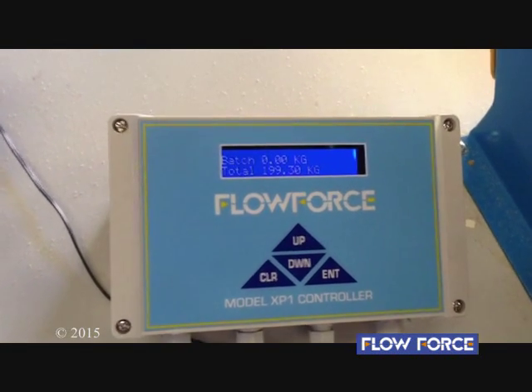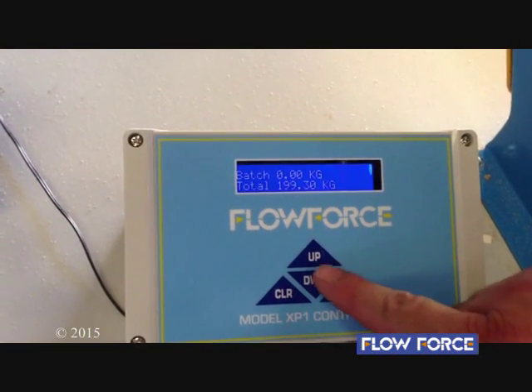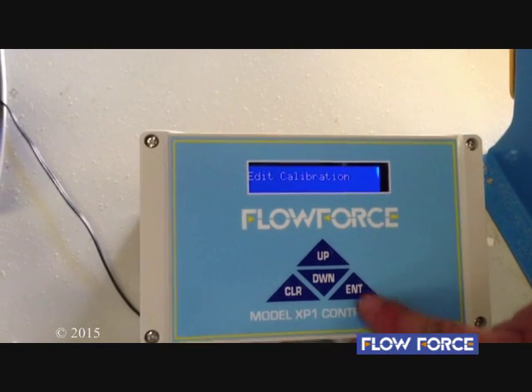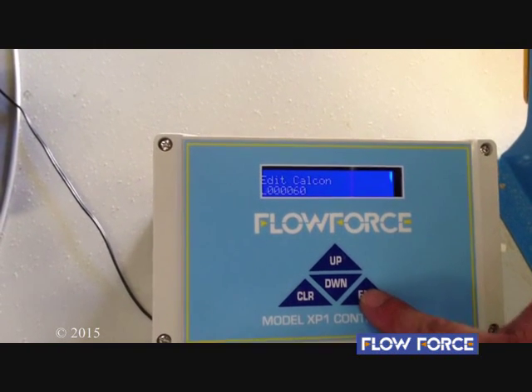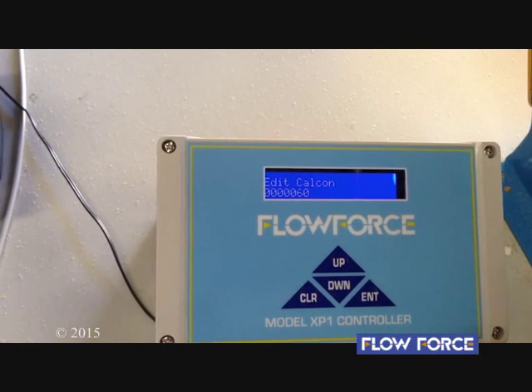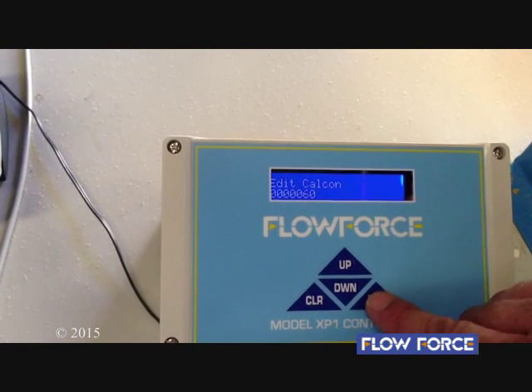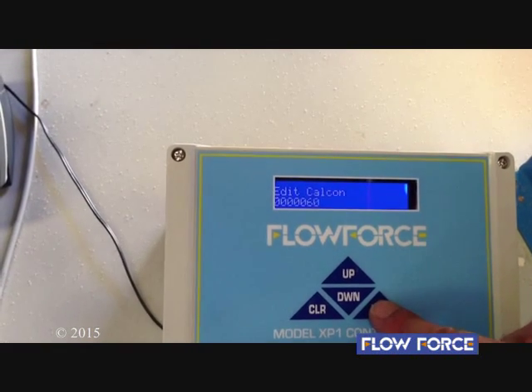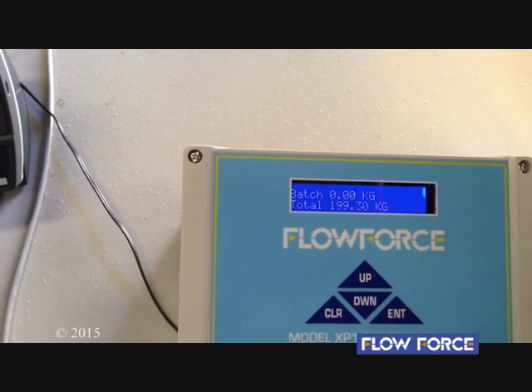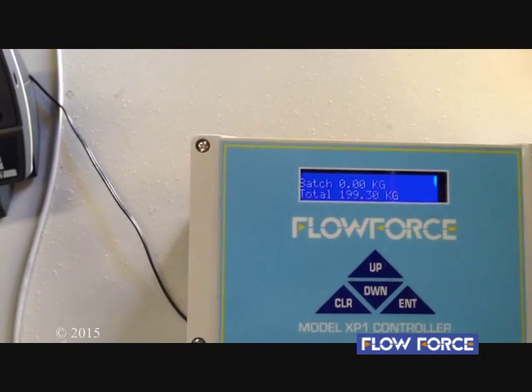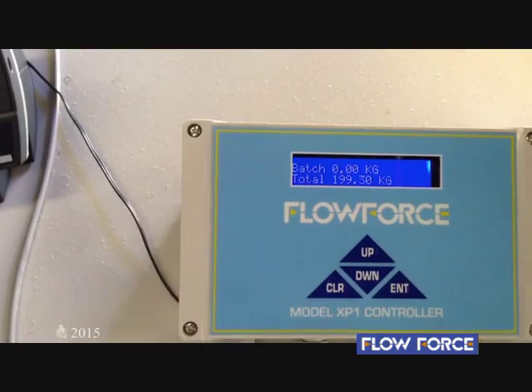Before we start the test, we should actually check what the Calcon has changed to, and we make a note of this. So we've got to edit calibration, and you'll see in this instance that the Calcon has changed to 60. So you have to enter through those to get it to come back to 0. We're now ready to run test number 2.